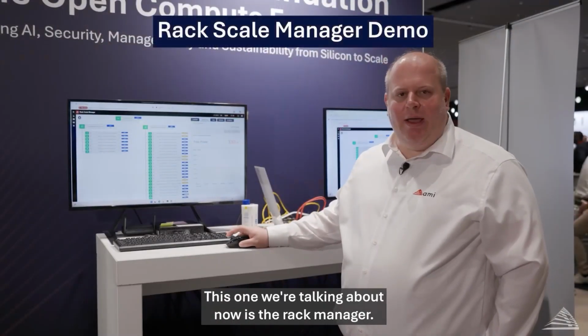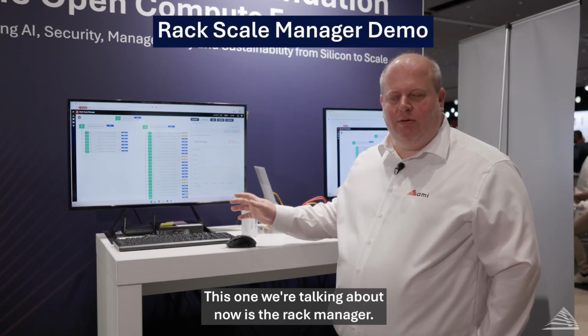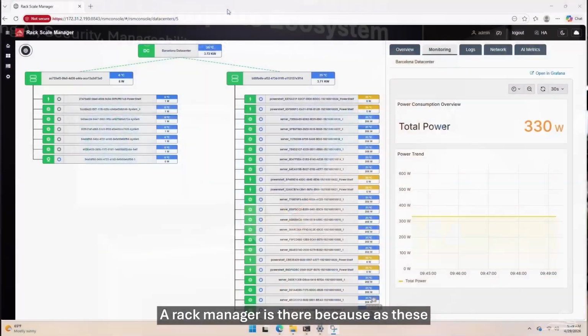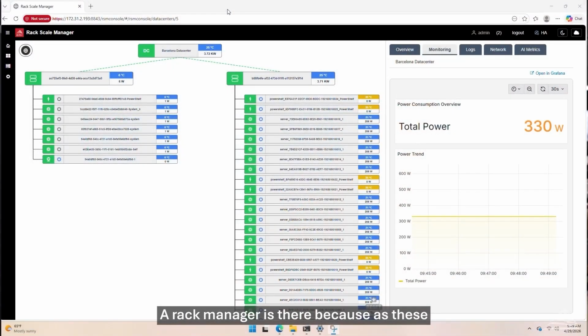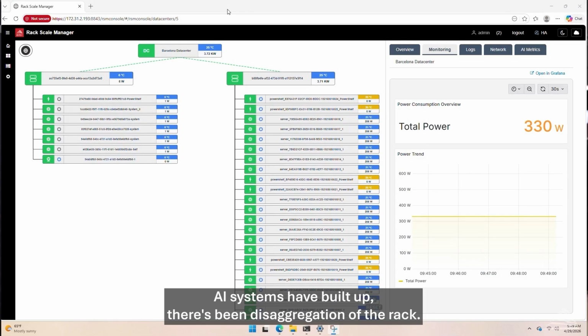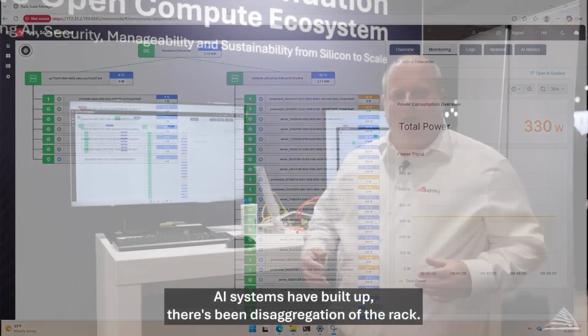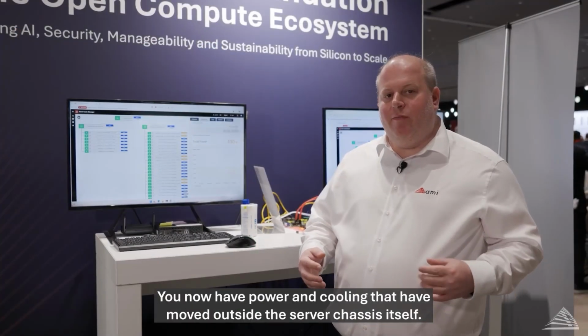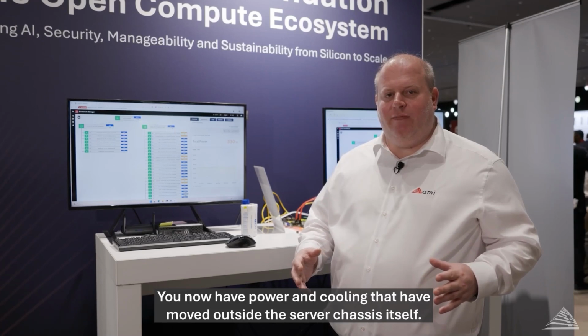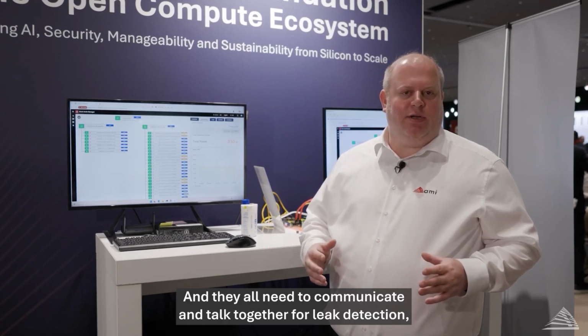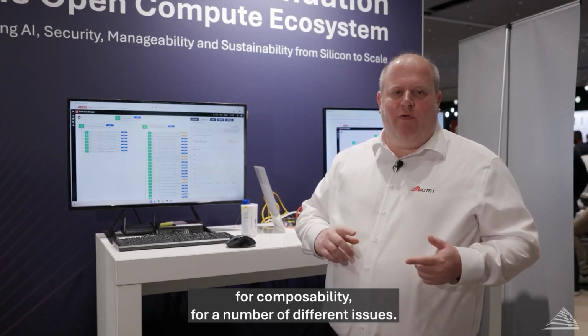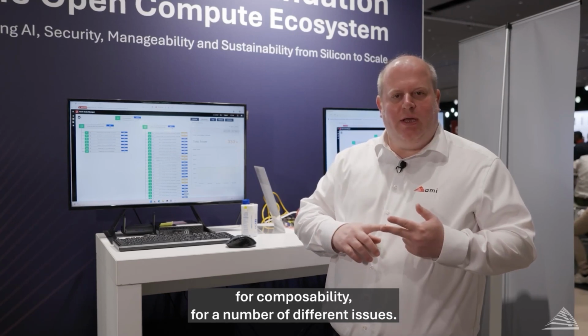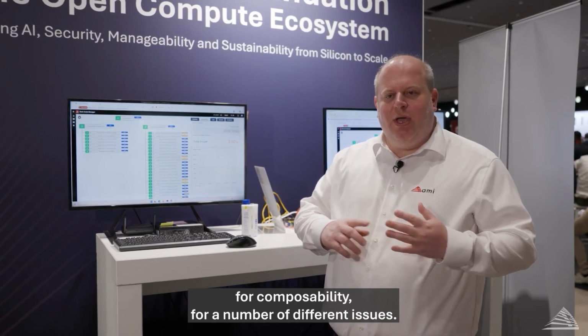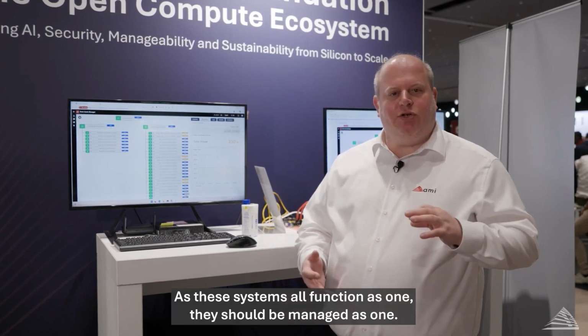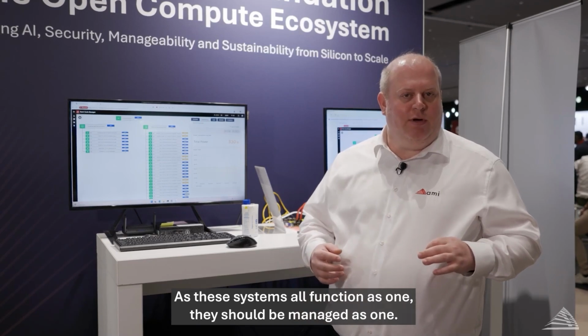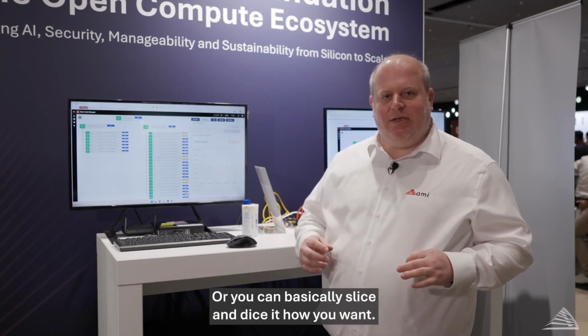This one we're talking about now is the rack manager. A rack manager is there because as these AI systems have built up, there's been disaggregation of the rack. You now have power and cooling that have moved outside the server chassis itself, and they all need to communicate and talk together for leak detection, for composability, for a number of different issues. As these systems all function as one, they should be managed as one, or you can slice and dice it how you want.